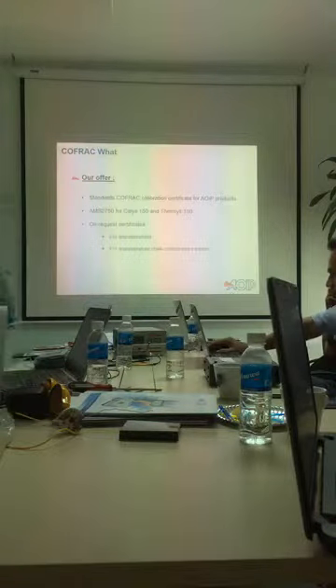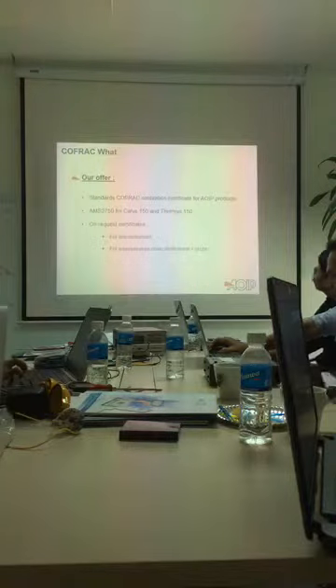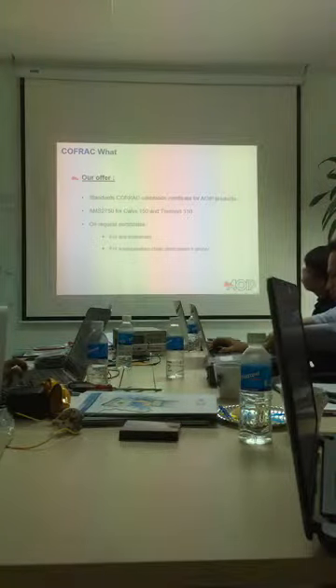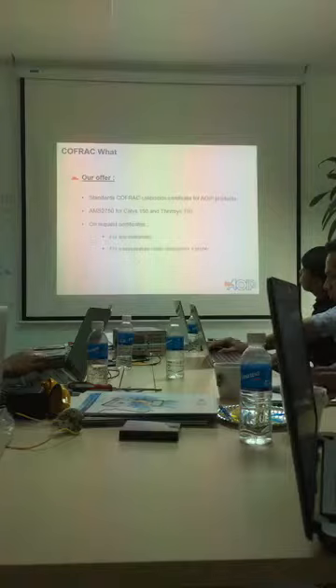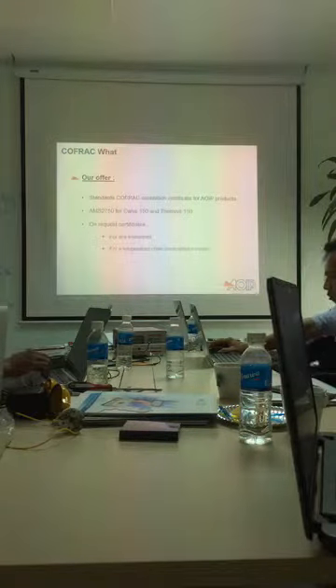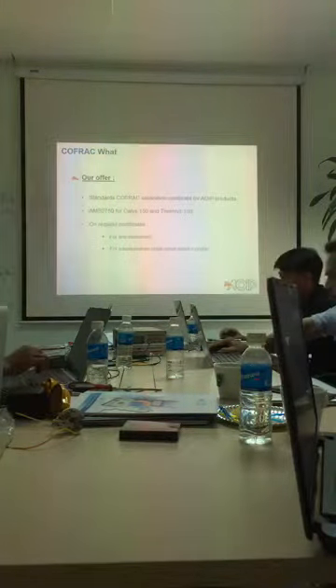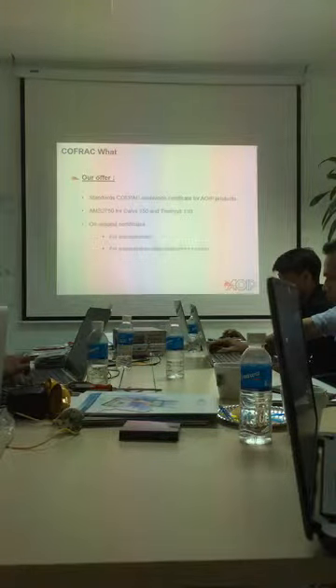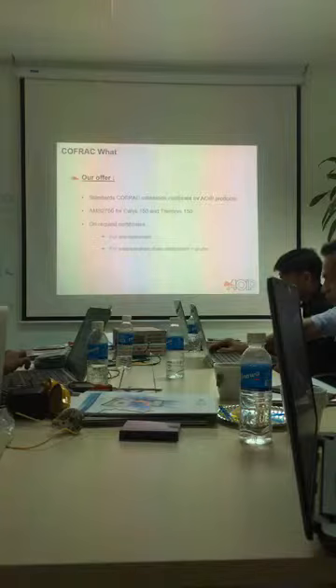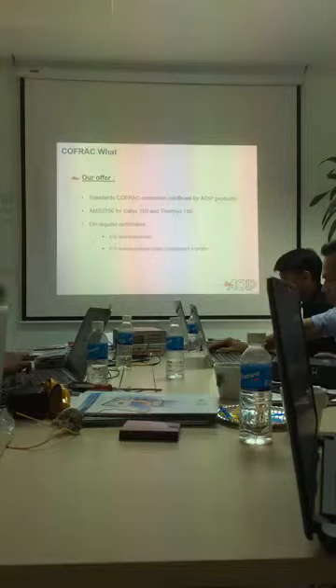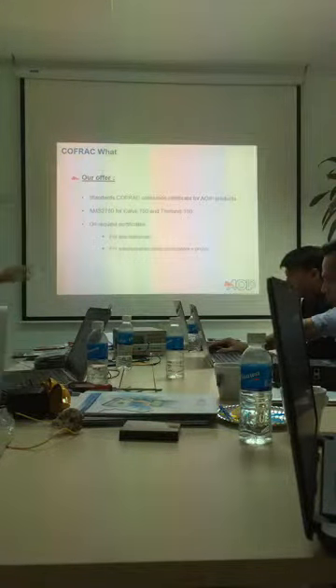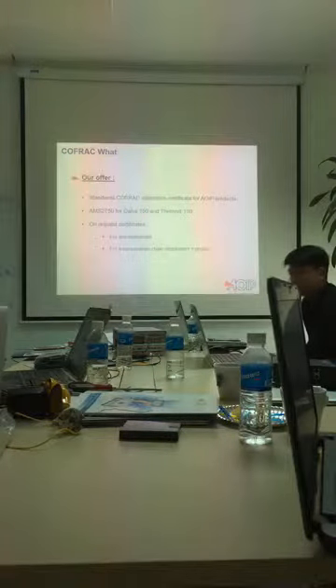What we have in our catalogs for calibration is a standard calibration certificate on all AOIP products. That means if a customer is asking for a standard calibration certificate, yes. If he tells you he wants a specific point on it, we will have to make a specific quotation. So why every time we ask you for a certificate for the OM 16, you say no, just the calibrator only? Yes, it's not the same thing.